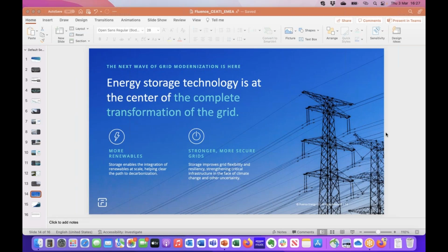It's not just about connecting and testing the storage technology and enclosure capability, but really looking at the communication protocol to the PCS, and also the PCS's capabilities. If there's a firmware change on the PCS, or a change in the overall power plant controllers, it really depends on the type of application we see.